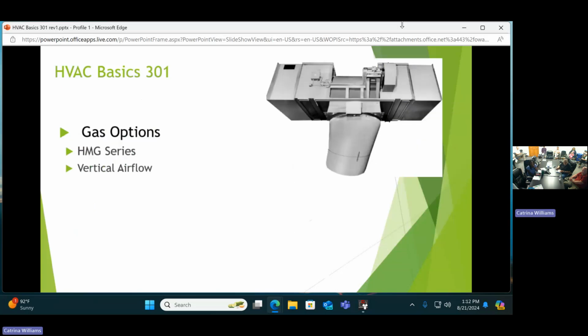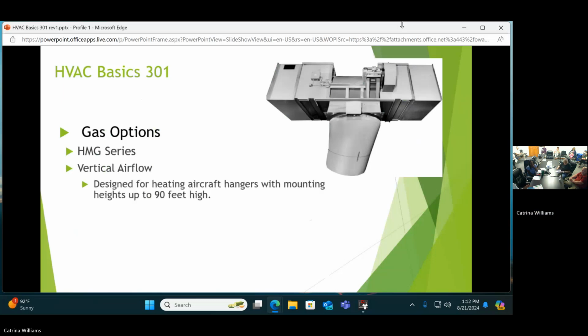And then the HMG, see the same looking picture up there. Same vertical airflow, but now we're using 4 indirect fired gas furnaces to provide the heat. And so we get rid of the steam or hot water coil and put duct furnaces there instead. These are the ones that you lower to the ground, right? No, this is up there on a high level again. These are really big units. But this goes up there to 90 feet or so that you can put them up there.